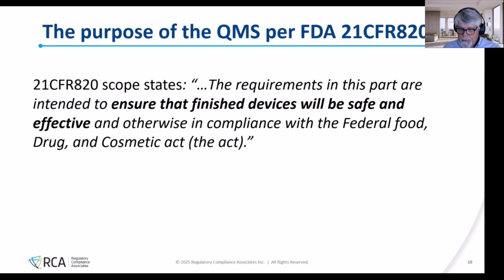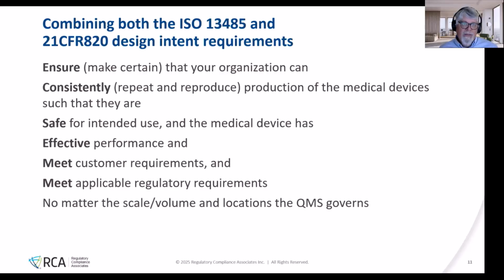Now, if we combine these bolded words that I had bolded, I combined 13485 and 21 CFR design intent requirements from both the scopes, then we get this list of terms that the bolded parts are coming from those two scopes. It says we must ensure, your organization must ensure that it means that you can consistently build product or repeat and reproduce the production of medical devices such that they are safe for intended use and the medical device has effective performance, meets its design intent, and meets customer requirements and meets applicable regulatory requirements, no matter the scale or volume and locations the QMS governs.